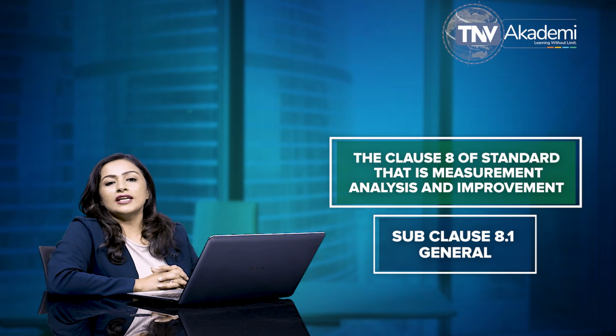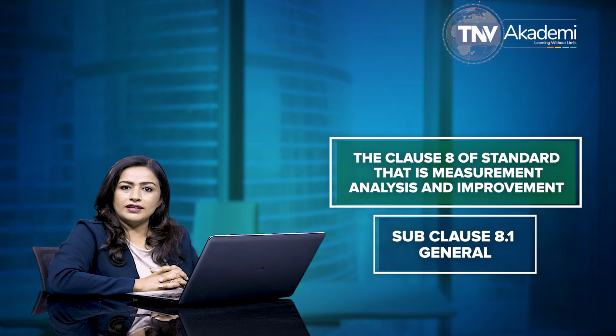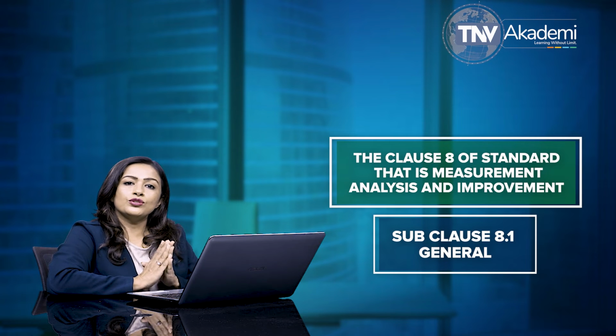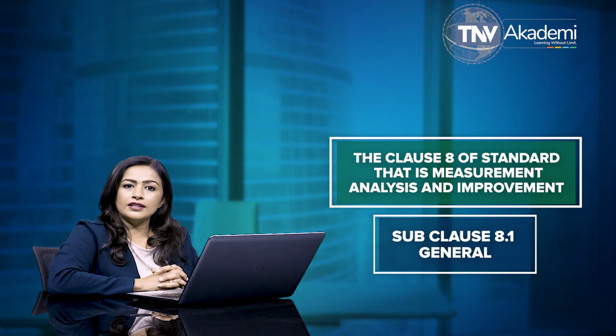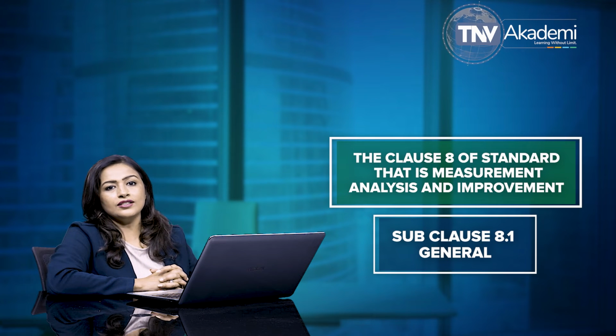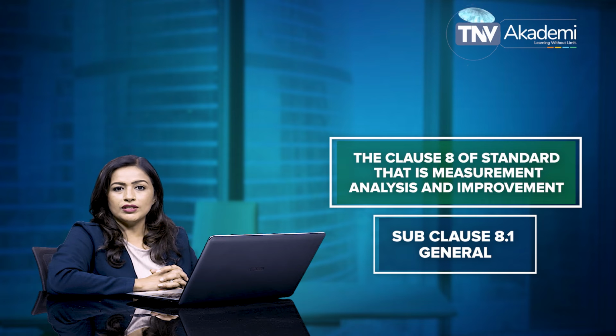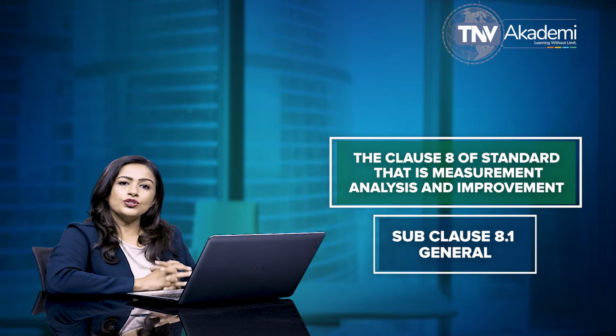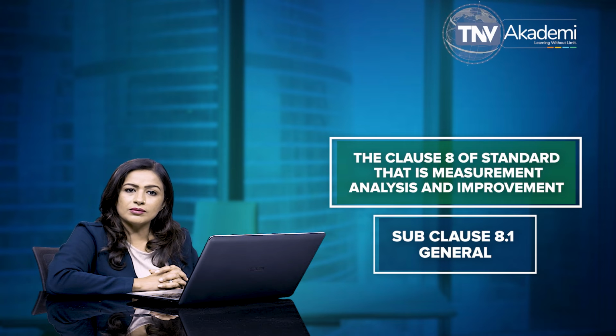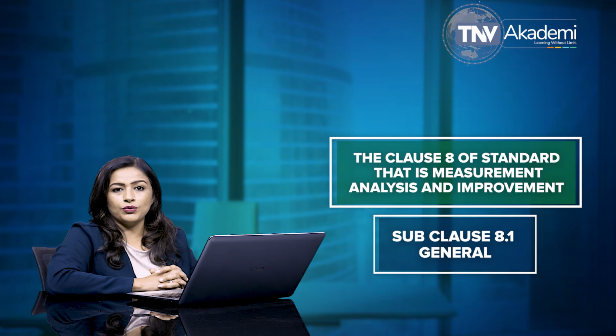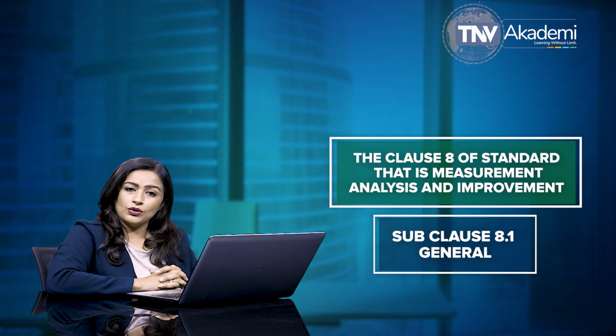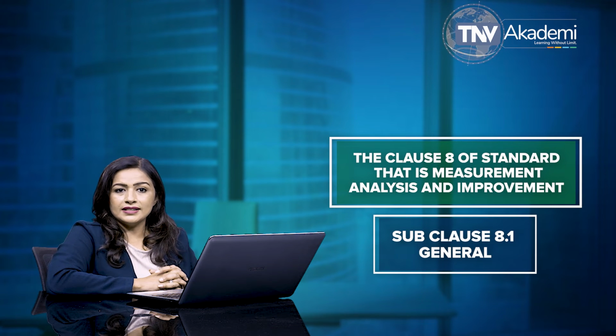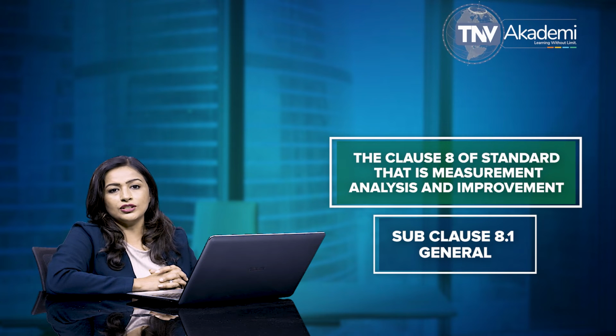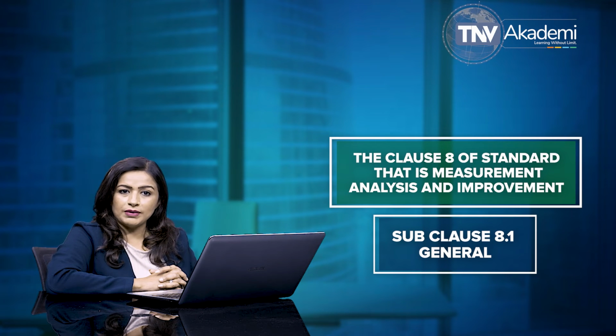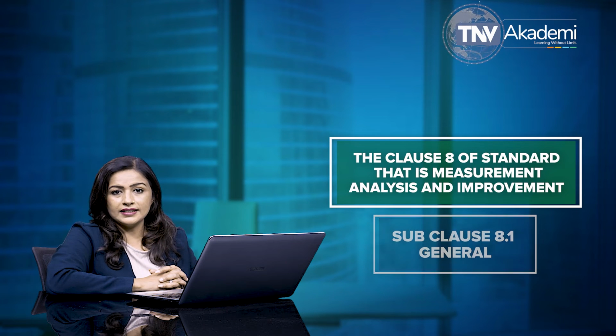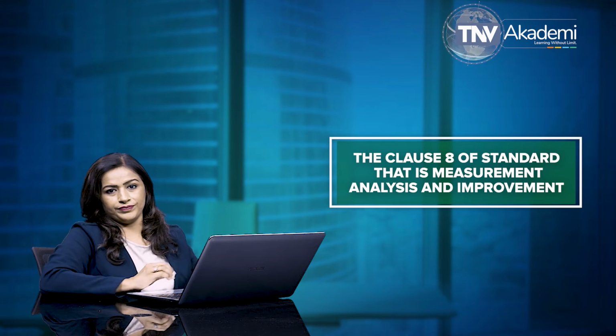According to this subclause 8.1 of ISO 13485, the organization is required to plan and implement the monitoring, measurement, analysis, and improvement processes needed to demonstrate conformity of the product, to ensure conformity of the quality management system, and to maintain the effectiveness of the quality management system. As per the clause, monitoring, measurement, analysis, and improvement processes must include determination of appropriate methods, including statistical techniques and the extent of their use.